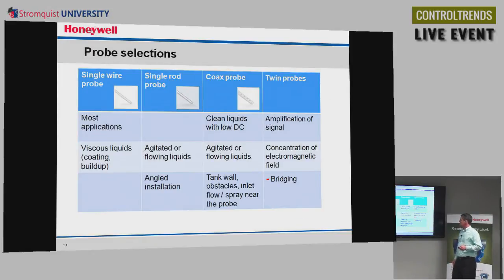For the different probe selections, we have the wire type probe, which is going to be used in most applications, and will go up to 150 feet. The single rod probe, and this would be segmented, will go out to about 30 feet in length. And in either case, we have to be concerned about the forces going from side to side, as well as the ones that are pulling on the probe. Coax probes give us a nice focused signal, but we have to make sure those are in clean kind of applications. Twin probes, same thing. That's going to focus the energy between the two, either cables or the rigid probes.